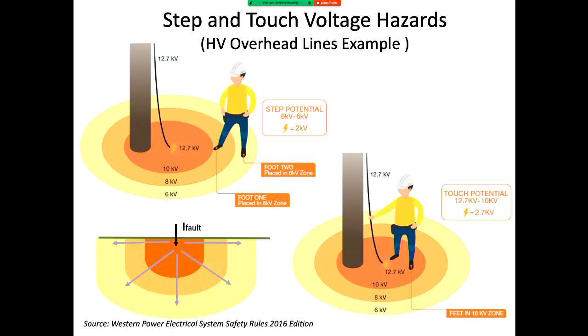Resistance relates to area: with a small area, you get higher resistance; as the area gets bigger, resistance gets lower. That's why close to the source you get steep voltage gradients. This is the case of step potential. You're not touching anything, but if you're close to it and your feet are spread apart, you can get a voltage difference of a couple of kV, which creates a current. That's called step potential.